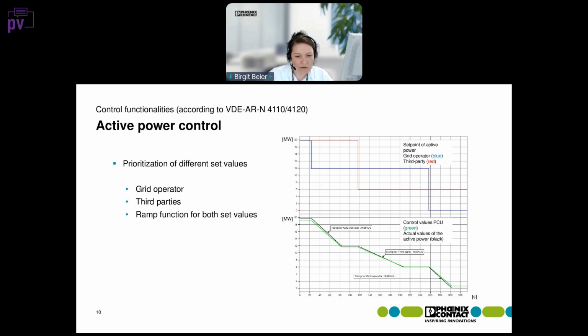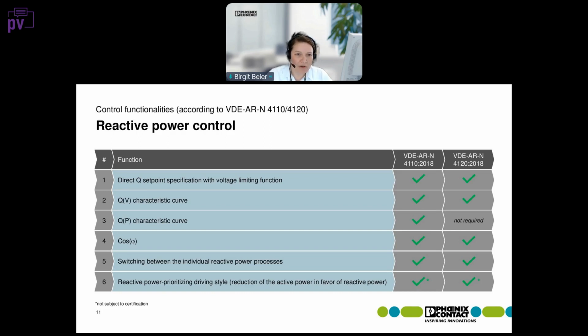Now we have another look at the reactive power control. In this, you have 6 functions for the reactive power control. First, you have, of course, a direct set point specification with voltage limiting function. You have 2 characteristic curves for reactive power as a function of the voltage. Then we have the reactive power as a function of the active power. Then you have the cosinus phi, so the power factor. Under 5, you can switch between the individual reactive power processes. And last but not least, reactive power prioritizing driving style, so you can reduce the active power in favor of the reactive power.